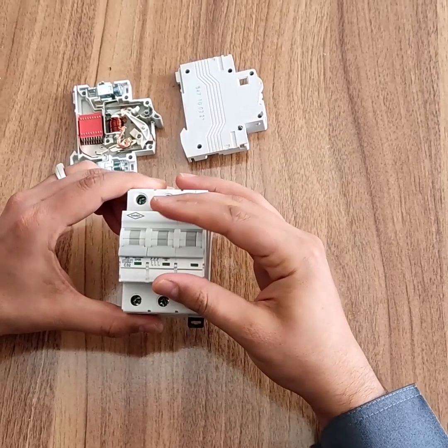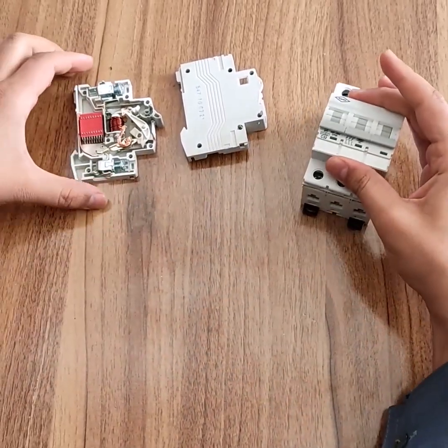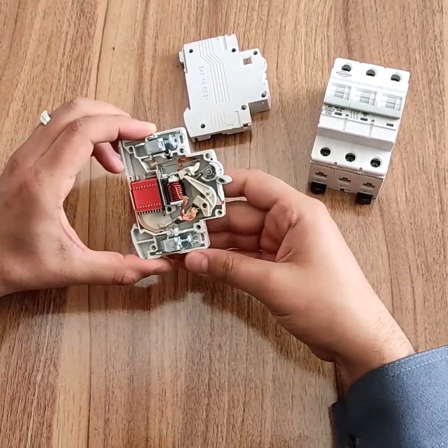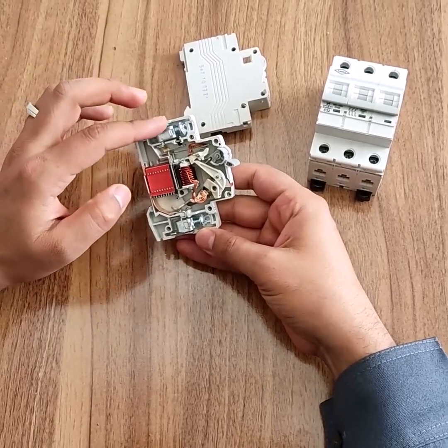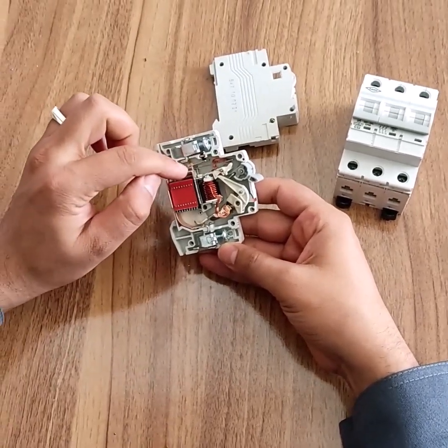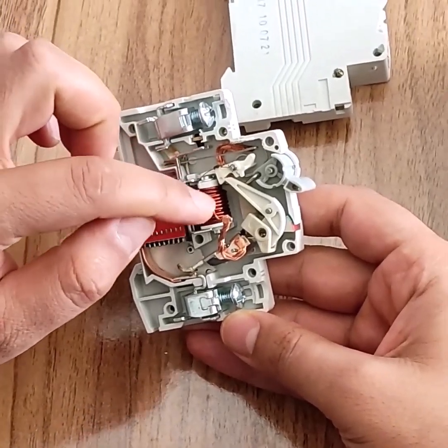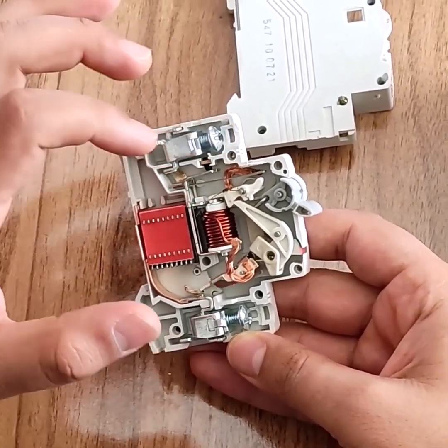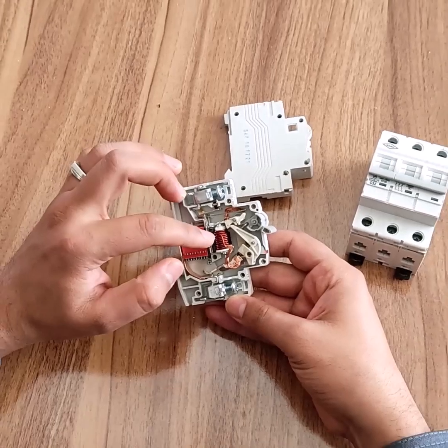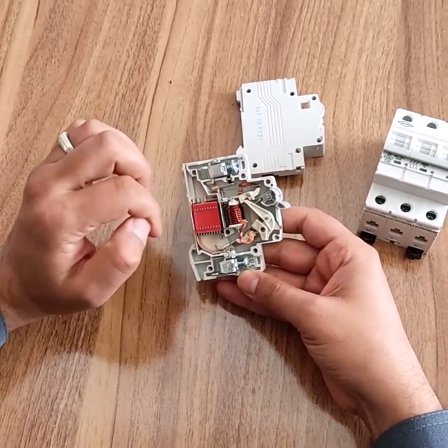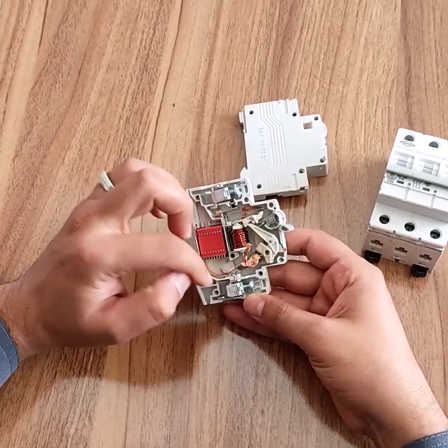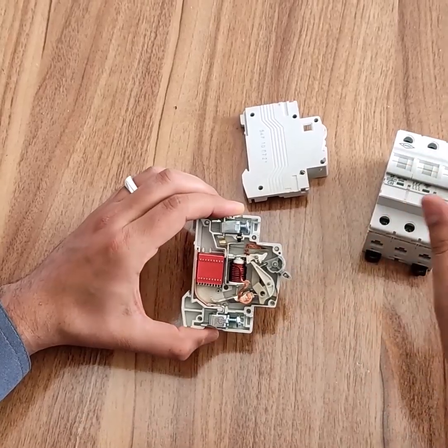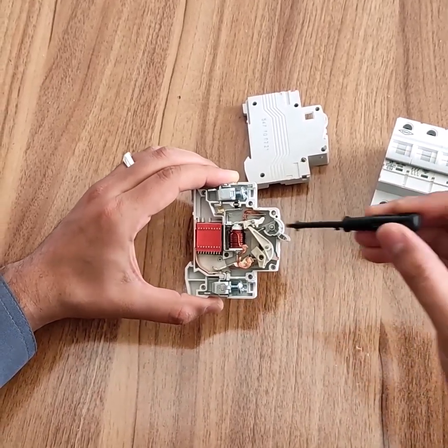It works like this. It is a single phase MCB device. As you can see, it is connected. The electricity input is connected from this part, and the bimetal is located here, and it is placed inside a coil from the bimetal part. This bimetal has the task of disconnecting against overload, and this coil has the task of disconnecting the load against a short circuit. And from this part, it is transferred to the output.